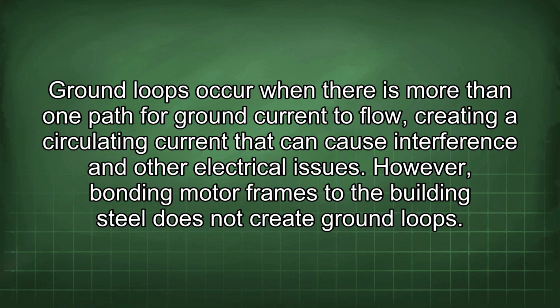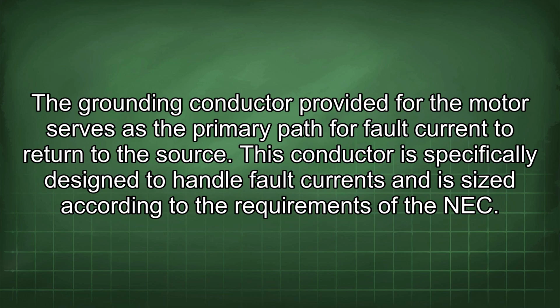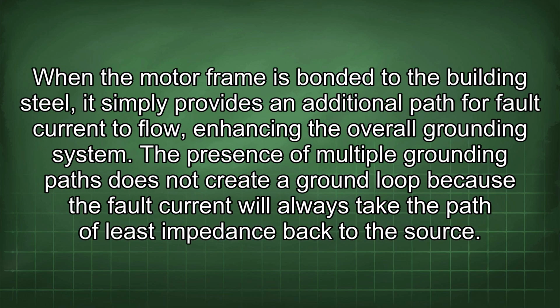However, bonding motor frames to the building steel does not create ground loops. The grounding conductor provided for the motor serves as the primary path for fault current to return to the source. This conductor is specifically designed to handle fault currents and is sized according to the requirements of the NEC. When the motor frame is bonded to the building steel, it simply provides an additional path for fault current to flow, enhancing the overall grounding system. The presence of multiple grounding paths does not create a ground loop because the fault current will always take the path of least impedance back to the source.